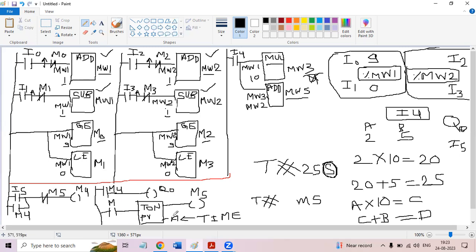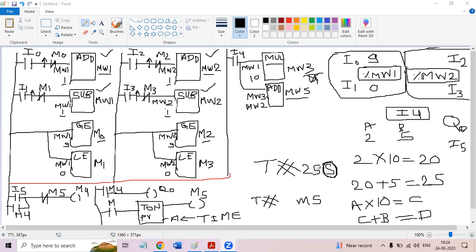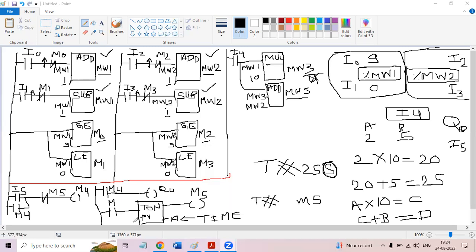And you remember in Codesys you have made a timer. In visualization, it was percentage MW1 divided by 1000. Why? Because it was running in millisecond, and we divided that by 1000 to make that second. So these two locations run in millisecond by default. As we type here T#25s, then it will run in second. But by default, it is millisecond.